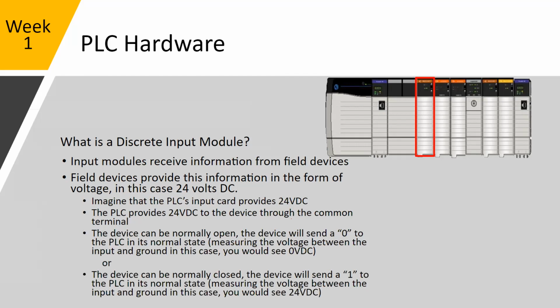What is a discrete input? Discrete can be used interchangeably with digital input. Input modules receive information from field devices. The field devices provide this information in the form of voltage, whether that's 24 volts. So imagine the PLC input card provides 24 volts DC. The PLC provides it to the device through a common terminal.